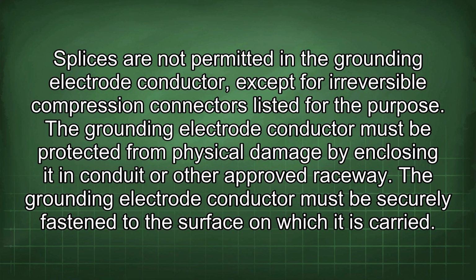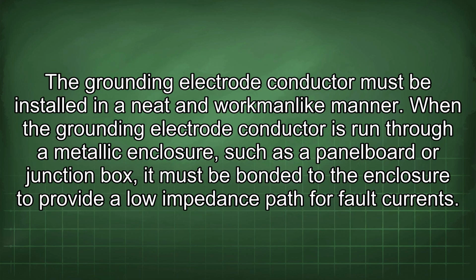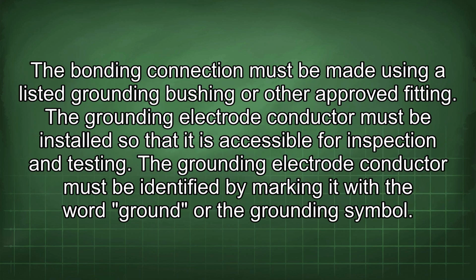The grounding electrode conductor must be protected from physical damage by enclosing it in conduit or other approved raceway. The grounding electrode conductor must be securely fastened to the surface on which it is carried. The grounding electrode conductor must be installed in a neat and workmanlike manner. When the grounding electrode conductor is run through a metallic enclosure, such as a panel board or junction box, it must be bonded to the enclosure to provide a low impedance path for fault currents. The bonding connection must be made using a listed grounding bushing or other approved fitting. The grounding electrode conductor must be installed so that it is accessible for inspection and testing. The grounding electrode conductor must be identified by marking it with the word ground or the grounding symbol.